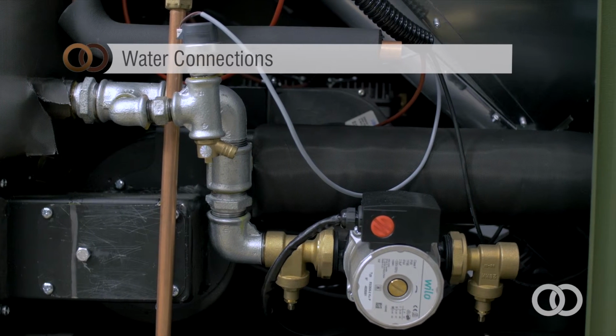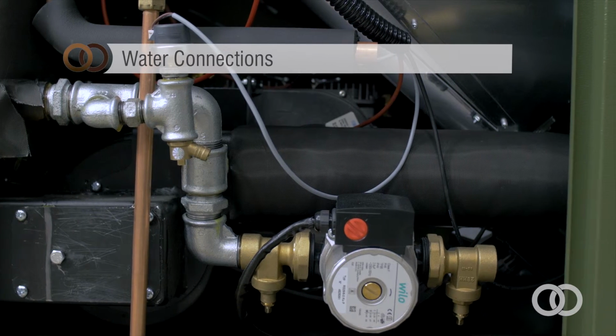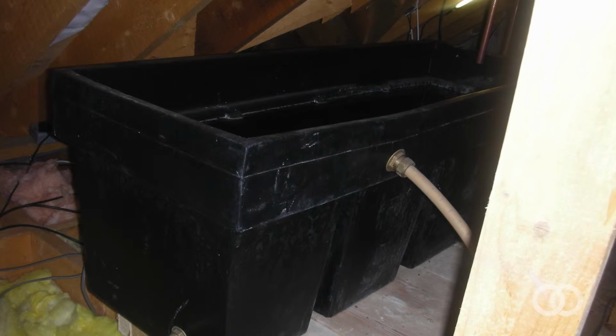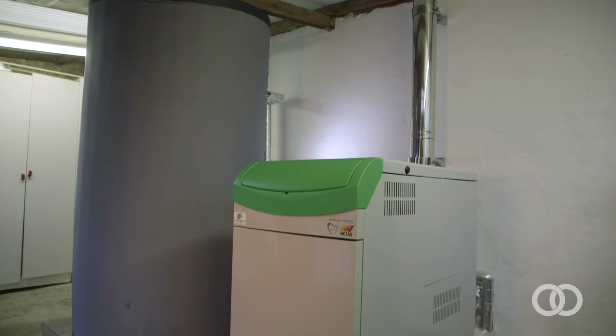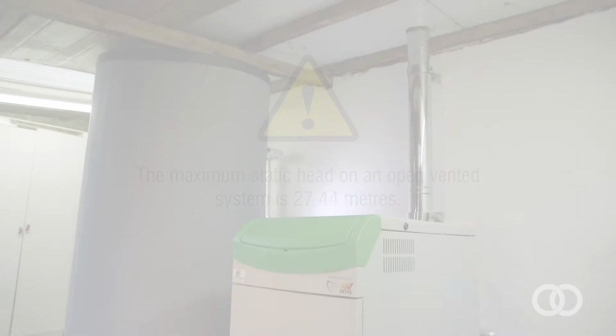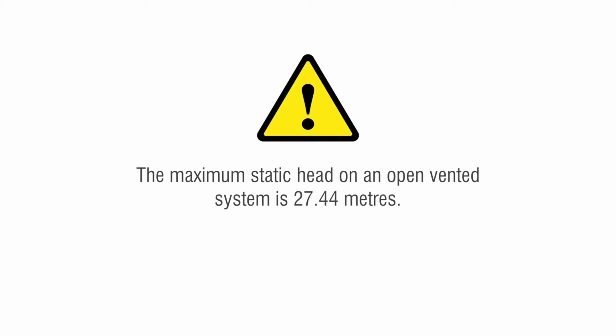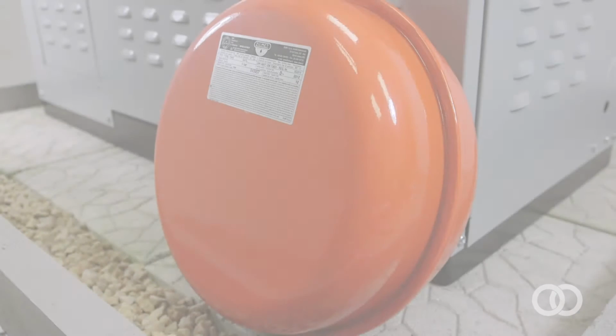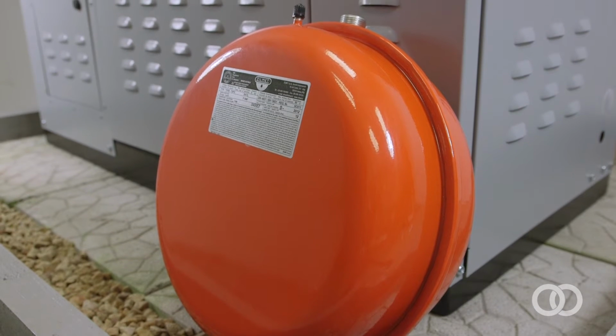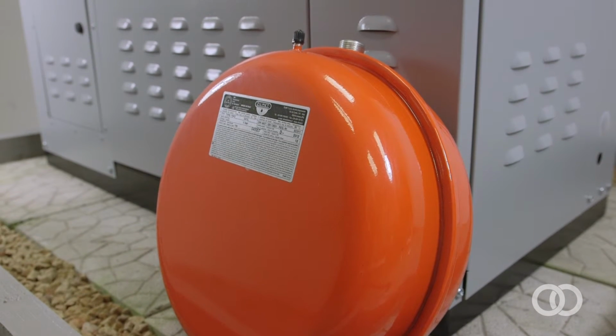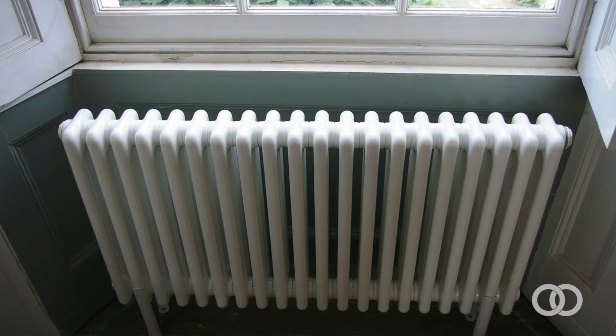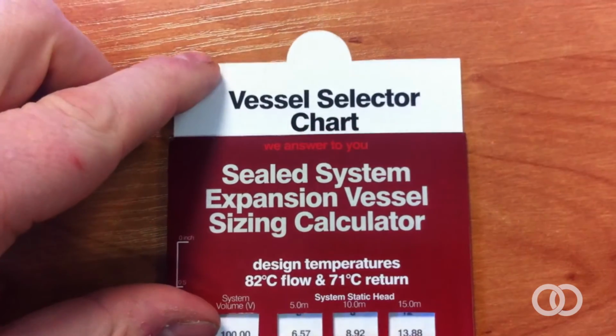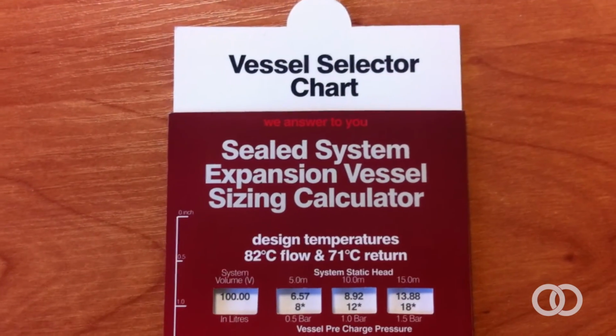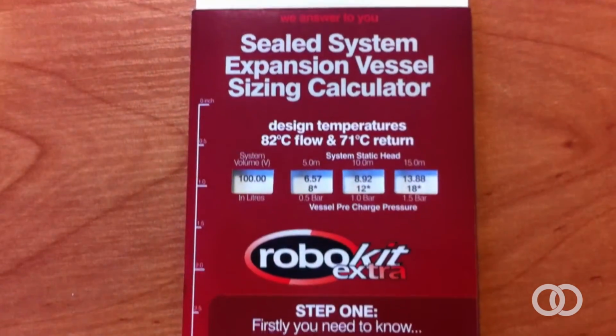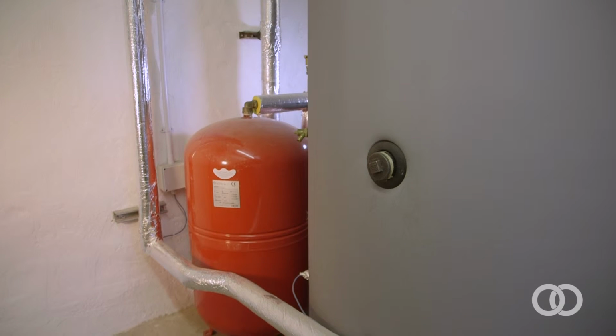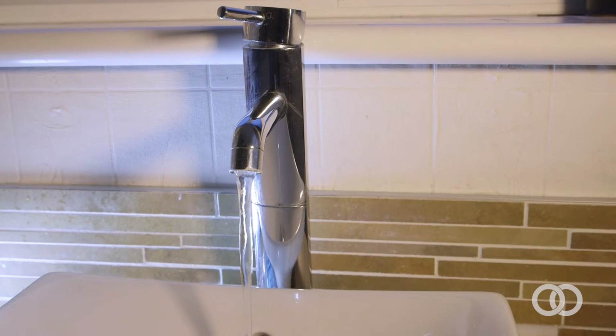Water connections. The flow and return connections are on the right hand side of the boiler. The boiler can be plumbed into either an open vented or sealed pressurized system. The maximum static head on an open vented system is 27.44 meters. If on a sealed system, the expansion vessel must be installed as per the manufacturer's instructions and based on the water capacity in the boiler and the entire heating system. Failure to size the expansion vessel correctly may cause the boiler to leak over time and invalidate your warranty. A minimum 18-litre vessel is recommended plus additional expansion for the heating and domestic hot water.